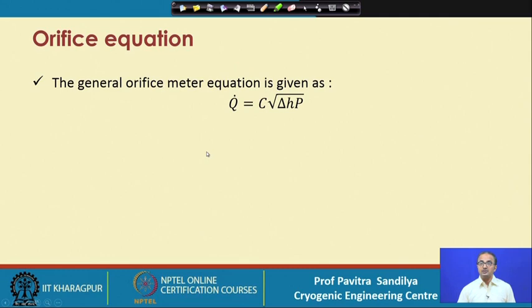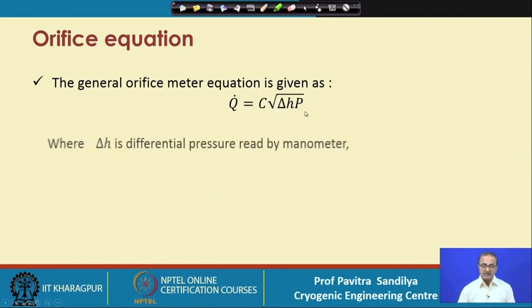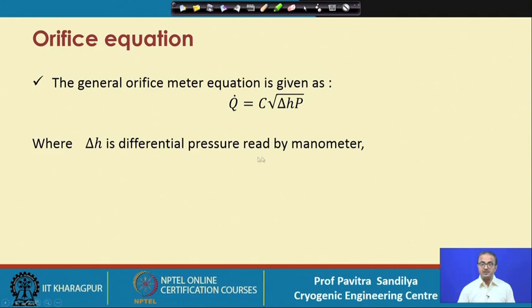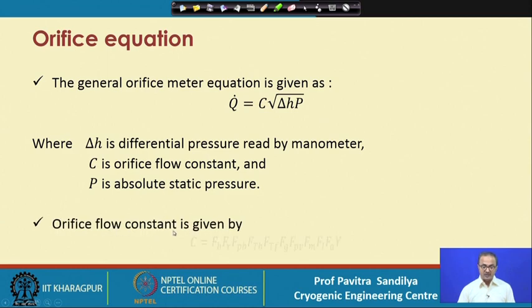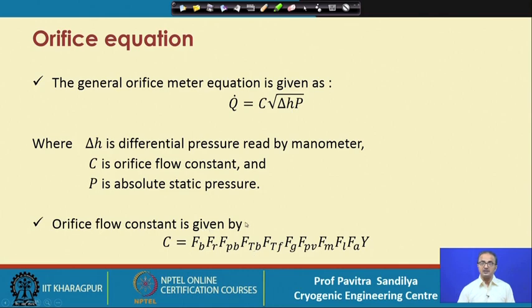In the natural gas industry, the flow equation is expressed as Q = C√(ΔhP), where delta h is the differential pressure measured by the manometer, C is the orifice flow constant, and P is the absolute static pressure. The orifice flow constant is given in terms of many correction factors.